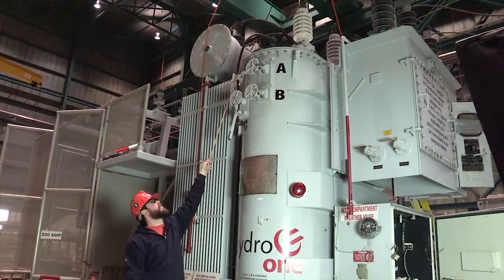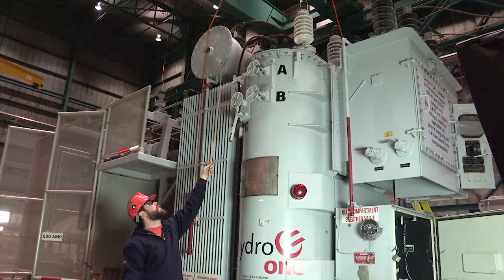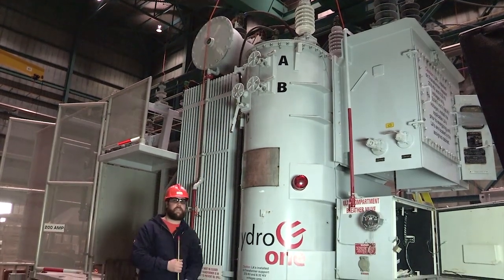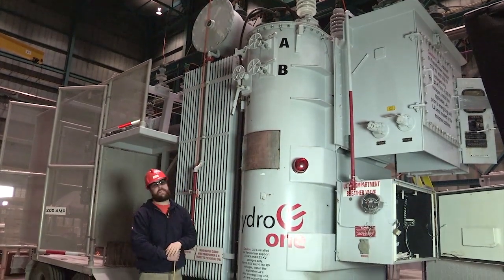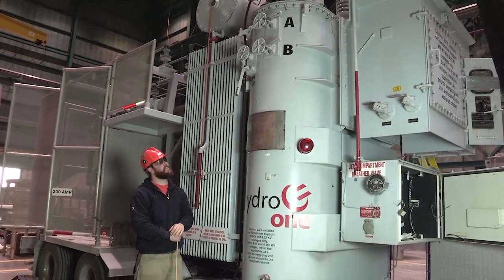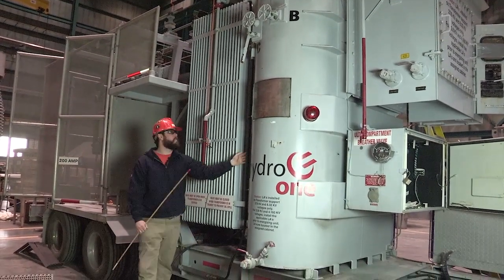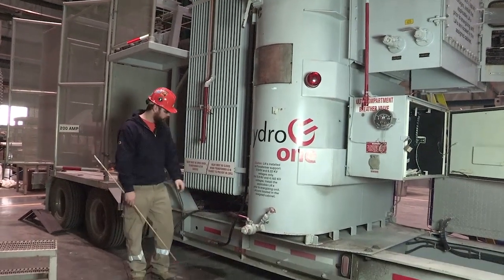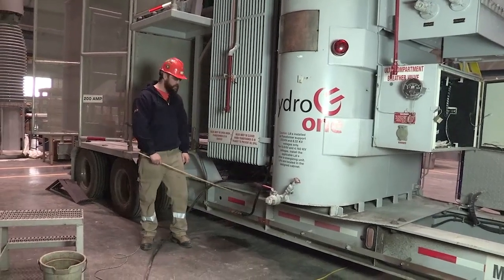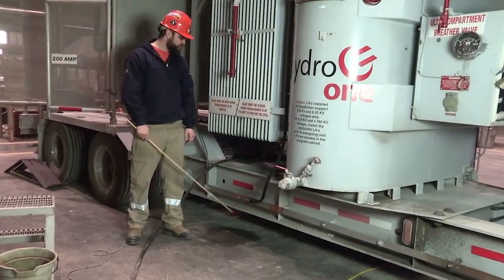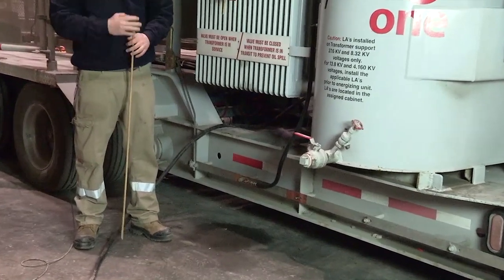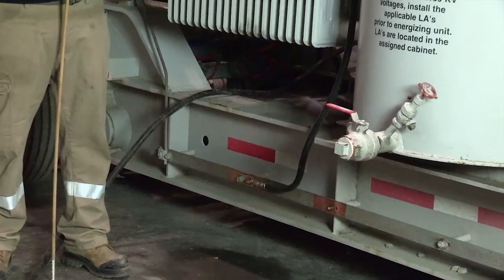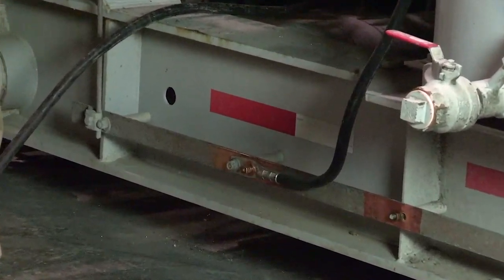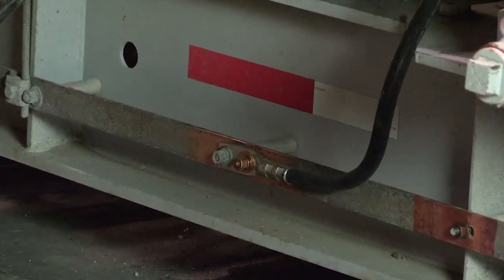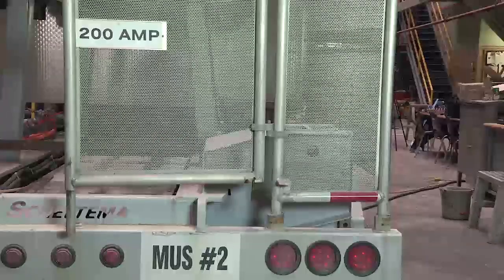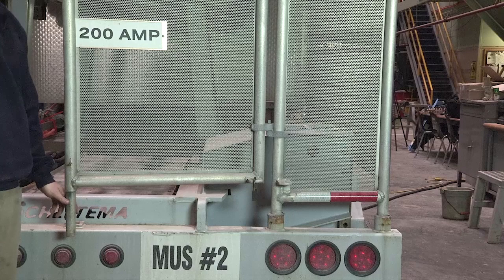Next, we're going to look at the neutral. We're going to inspect the neutral bushing clamp. A lot of times that will get overstretched from over-tightening from being removed and reconnected so many times. And just inspect the neutral as it comes down the transformer. And once it gets to the bottom, it's a good thing to inspect the connection made to the ground bus, because like we talked about earlier, theft and other things down in the field you might not pick up and notice.